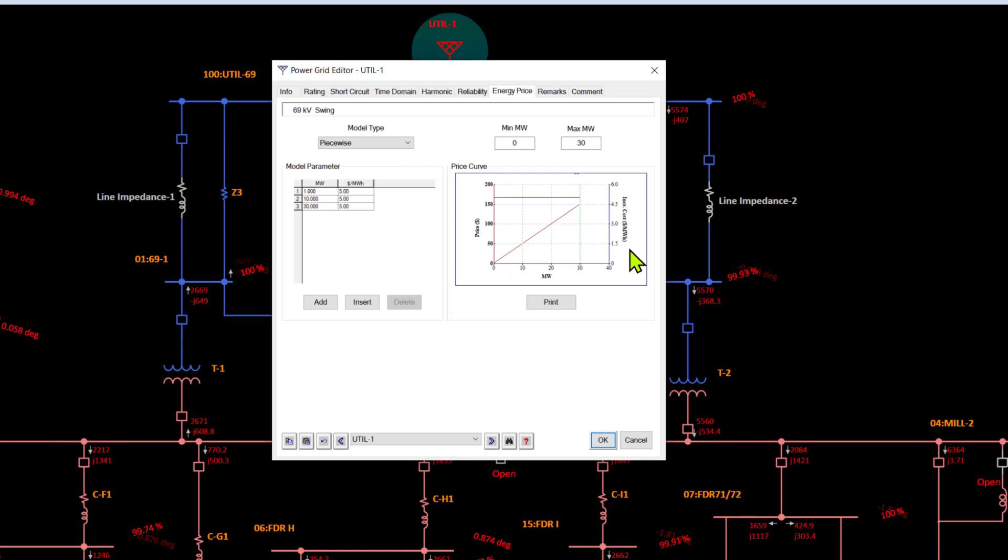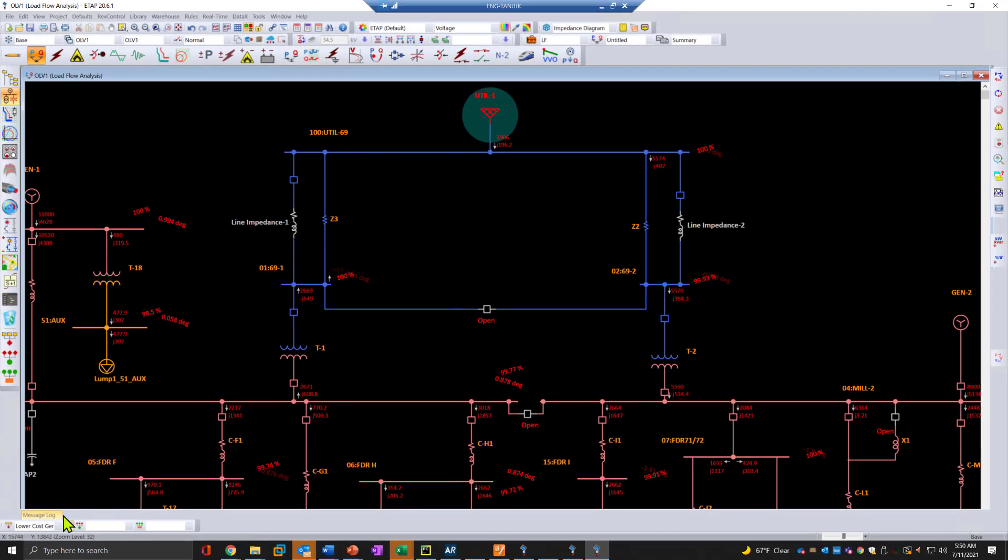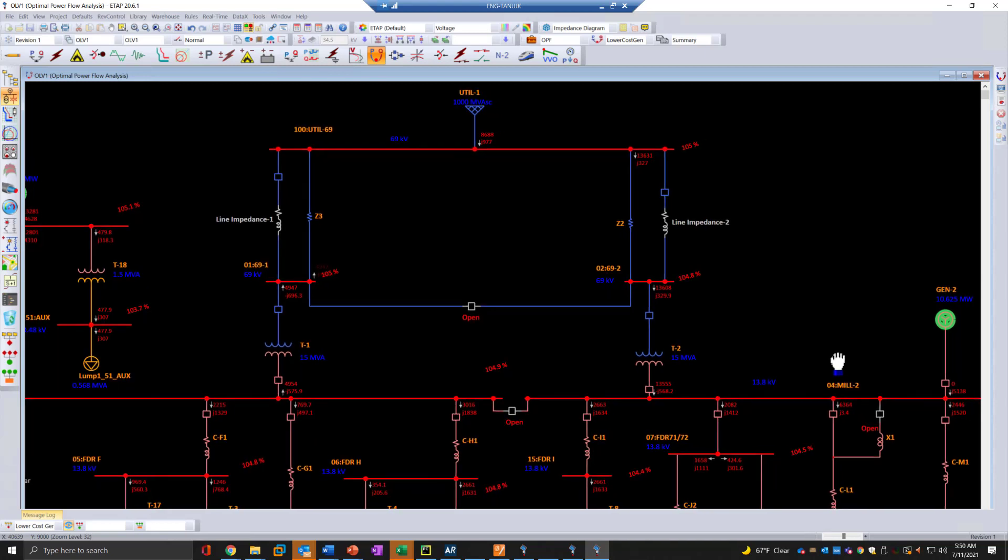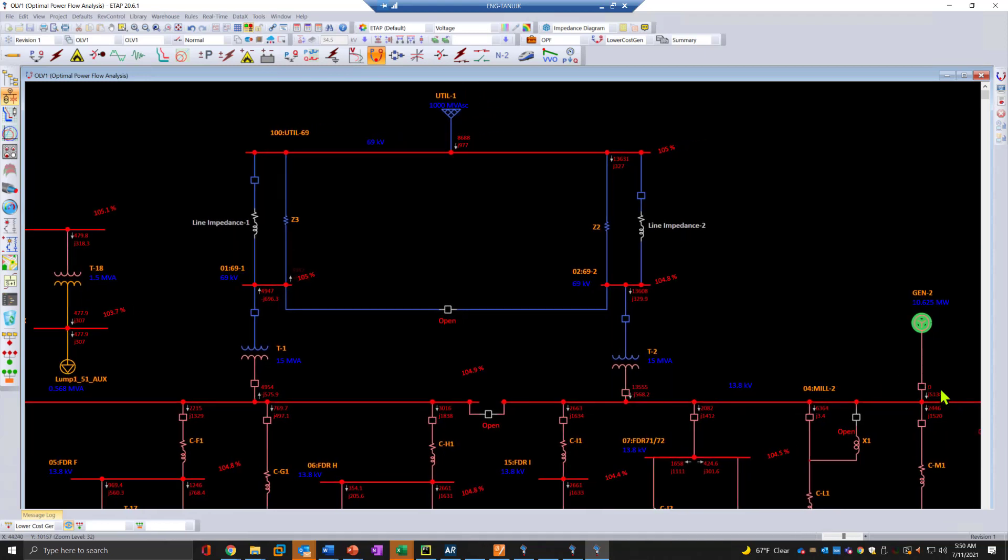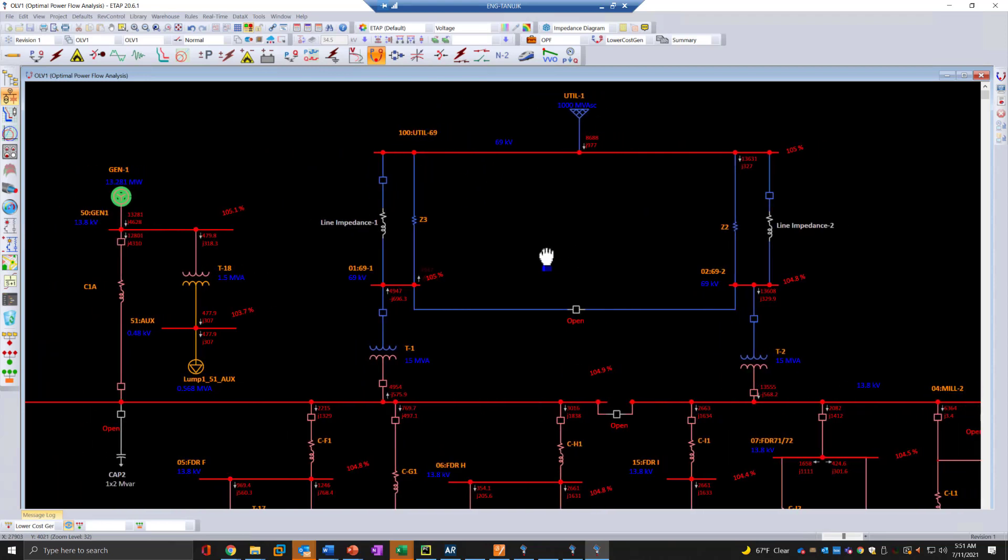The first scenario that I've already created in the interest of time is when we want to minimize the cost on the system such that generator 1 is actually the cheapest source, while generator 2 is not the cheapest source. Here we can see OPF rebalancing such that we are using generator 2 purely for its reactive power and not the real power output. The grid power goes from 3 megawatt to 8.6, and generator 1 takes up maximum load and reaches its rated limit of 13.281 megawatt.